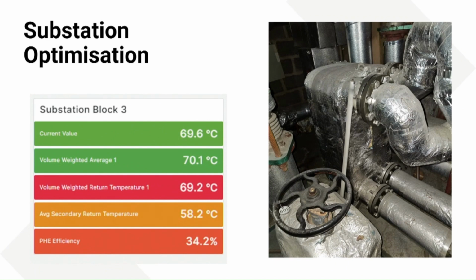Substation optimization - we do loads of substations, they're everywhere on the city schemes. You've got your normal things like flow rates and temperatures. We've been working on a metric to describe a plate heat exchanger efficiency figure, which I'll go into a bit later, but it's a nice figure - it basically tells you if a plate's working, and how close the approach temperatures are. So here we have a secondary return of 58, but it was going back to the network at 69 - that's really poor efficiency, which is reflected in the metric.